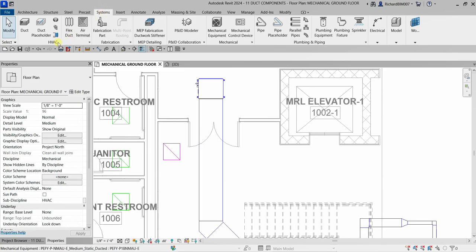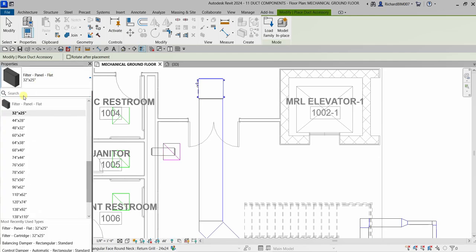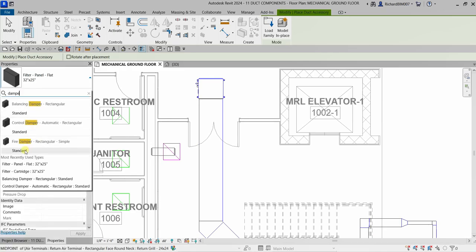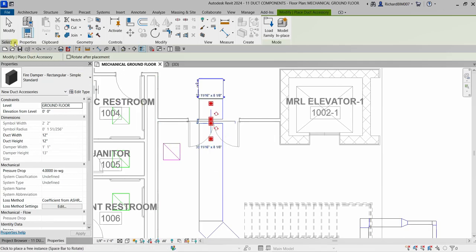From the HVAC panel, click 'Duct Accessory' — the shortcut is DA. From the type selector, search for the accessory you want. I'll type 'damper' and select 'Fire Damper Standard.' Then click on a duct to place the instance of the damper.